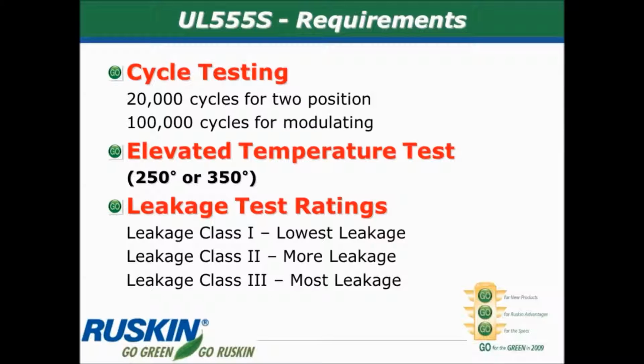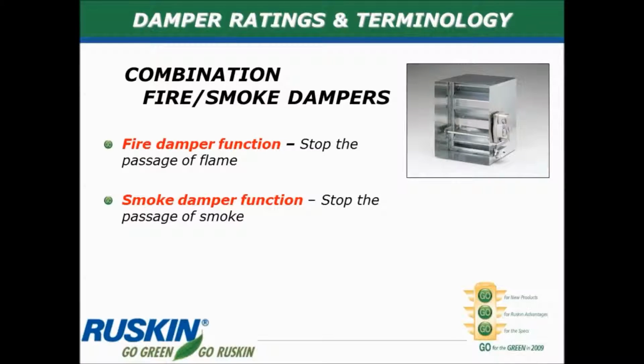Class 1 is by far the best, allowing only 8 CFM of air or smoke to pass through at 4 inches of pressure. Now, quite often today, partitions within buildings are rated for both fire and smoke. Now, you could install 2 separate products. You could install a fire damper in the plane of the wall and then a smoke damper within 24 inches of that. But why install 2 separate products when you can install one combination product? And the combination fire smoke damper is designed to stop both the passage of flame, that's the fire damper function, and designed to stop the passage of smoke, the smoke damper function.